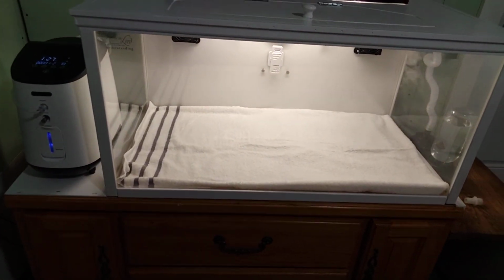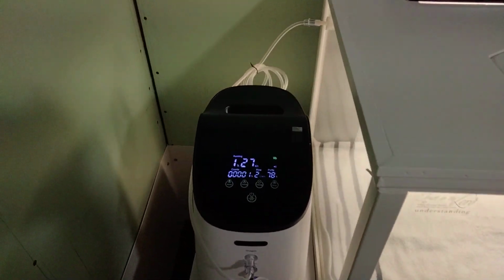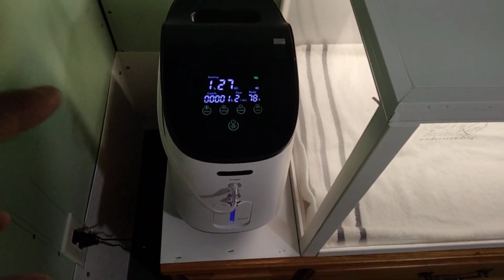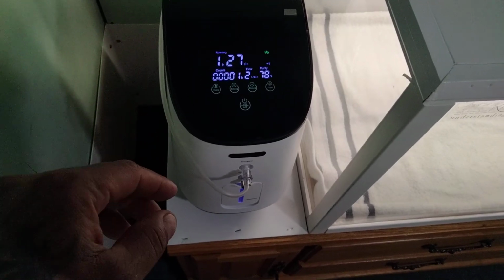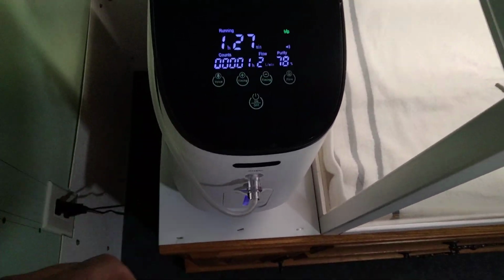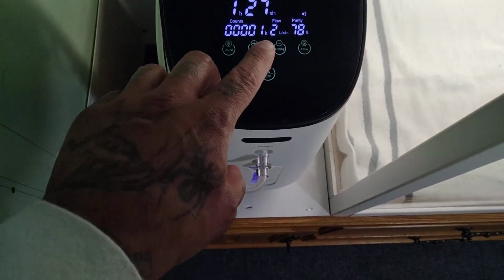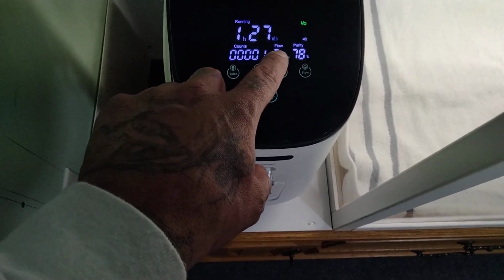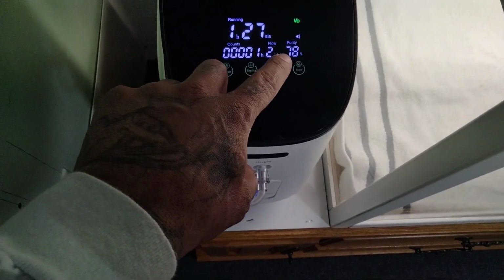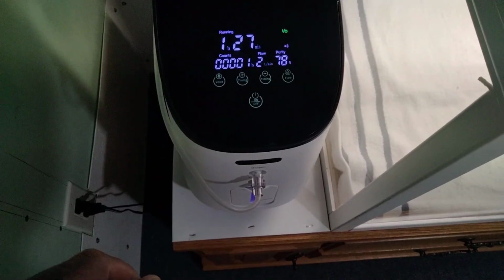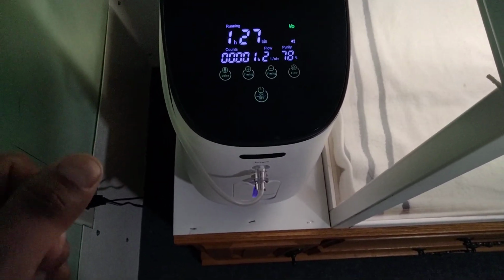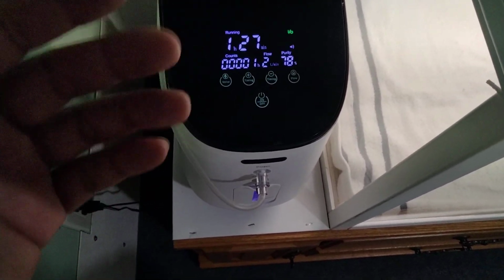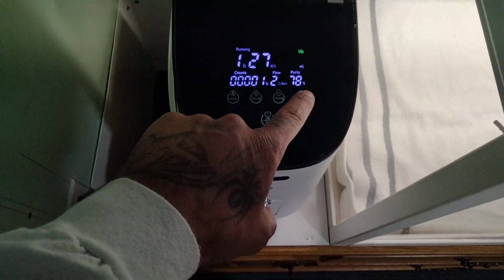Right now this is the oxygen machine. It's been running an hour and 27 minutes, supplying 1.2 liters a minute. The purity of oxygen is about 78%. That's actually supplying to the incubator, and I can change the flow here.